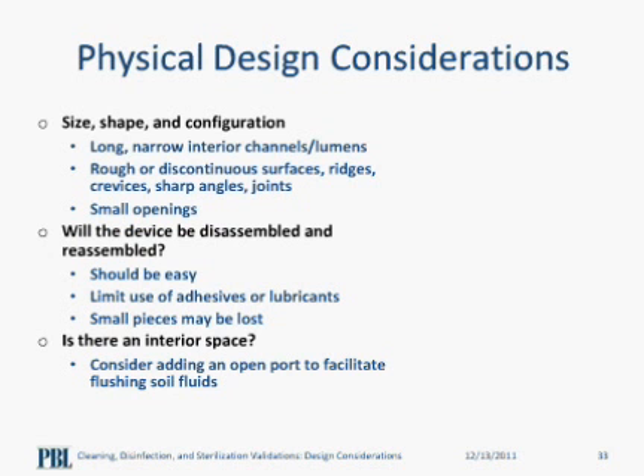A small opening is a very good site for corrosion because it allows an aggressive, strong solution to stagnate and possibly form red rust around its narrow opening. One thing more, it may not permit a common brush to pass through and clean the interior surface of the device unless a special kind of brush is designed for that particular device. Rough, irregular, and discontinuous surfaces, and the presence of ridges, crevices, sharp angles, and joints are difficult to clean. These areas can trap or retain microorganisms and impurities such as the patient's blood and other body fluids or tissues, which are a good reservoir for microbial growth.